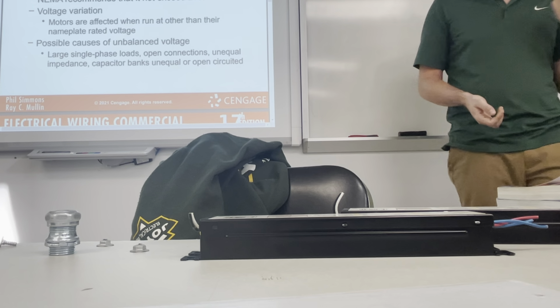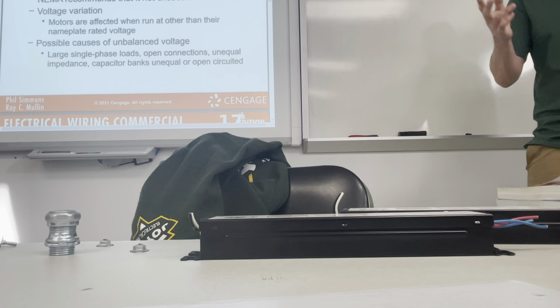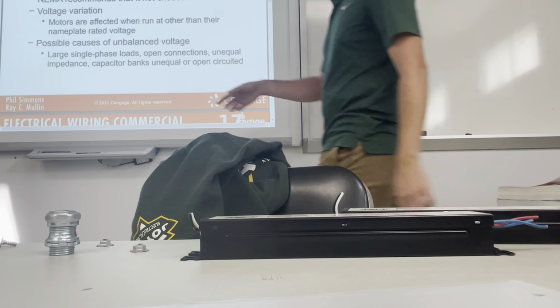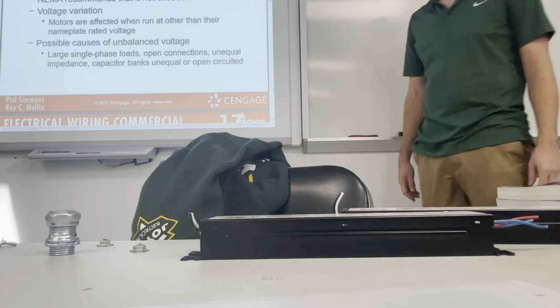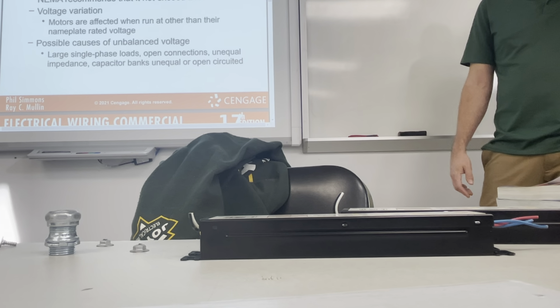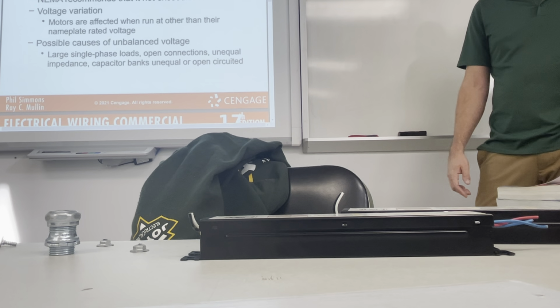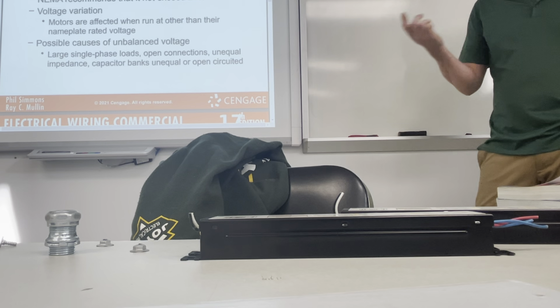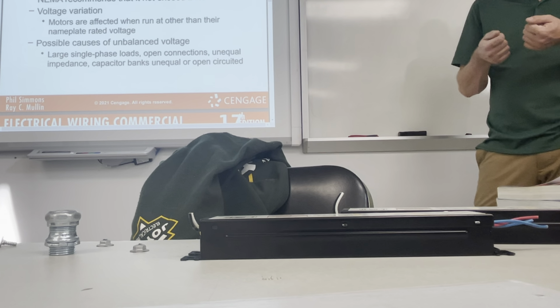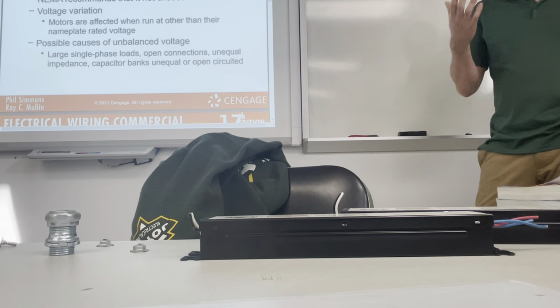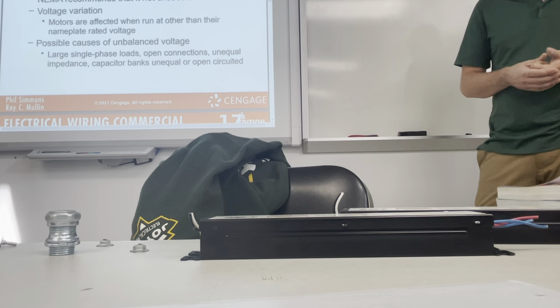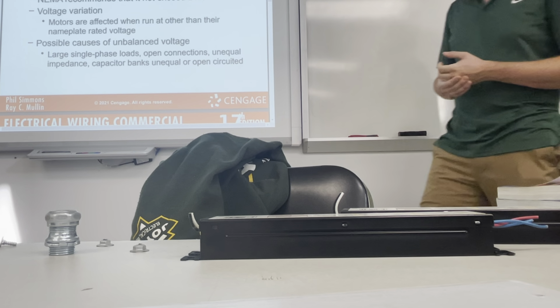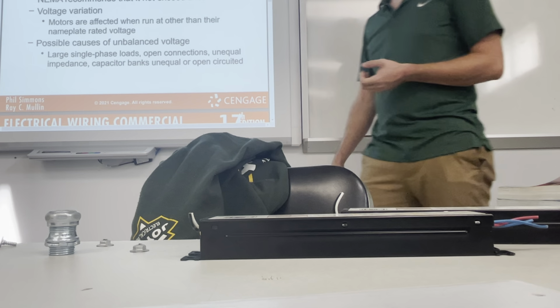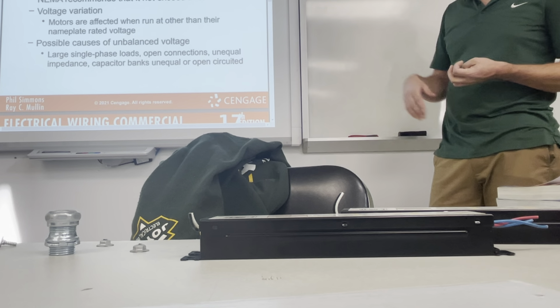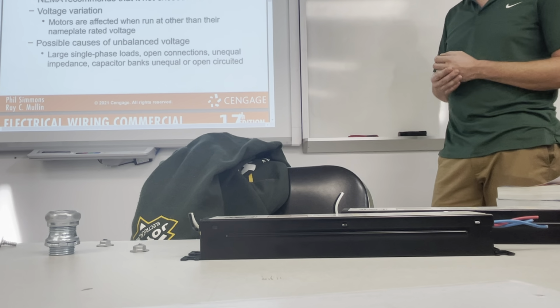No, there's a huge draw on only one, and the other two are basically untouched. That's going to cause the most unbalance. Or in the middle of summer when the heat is going, or when air conditioners run like crazy. When we go to a house, it's not uncommon to see like 235 instead of 240. Similar things like that can happen. The weather can play a factor, but 9 times out of 10, it's large single phase loads that are causing all that issue. Open connections, unequal impedance.